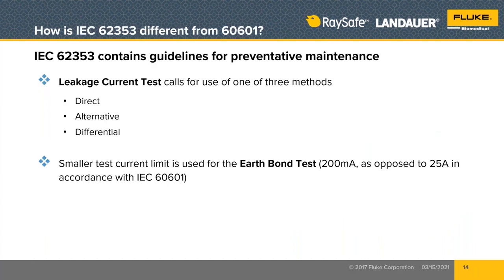IEC 62353 is the standard, but it doesn't have just one testing method and workflow and sequence of tests like the IEC 60601-1 does. IEC 62353 has 3 different test methods, and you have to choose which one you're going to use. Now, when do you choose that? You make that choice the first time that you do electrical safety testing, when you receive a new medical device that you've never had before in the hospital, a new brand or model of that medical device.